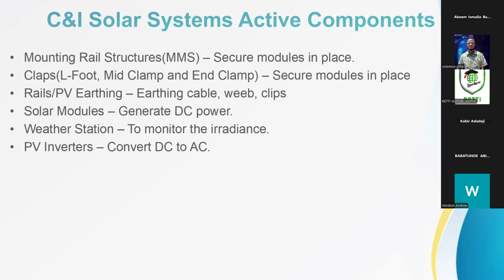Aside from that, if you are using a PV inverter, depending on the brand, you still need to talk to the manufacturer. There's something we call the characteristic curve. You need the characteristic curve. If not, they will just tell you that this PV inverter has an MPPT voltage of, let's assume, 1000. If you size your system based on that 1000, it means I can put 19 panels in a string. If you put those 19 panels in a string, you will realize that you can't generate up to the maximum, or you are not maximizing that particular PV inverter.